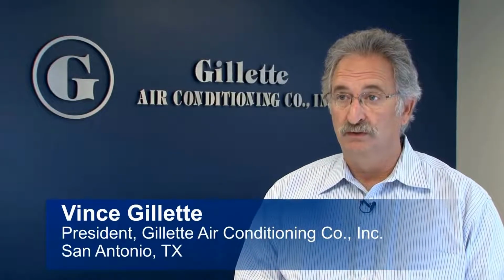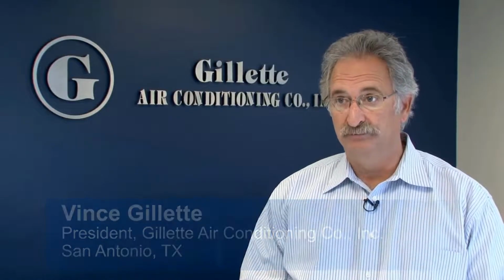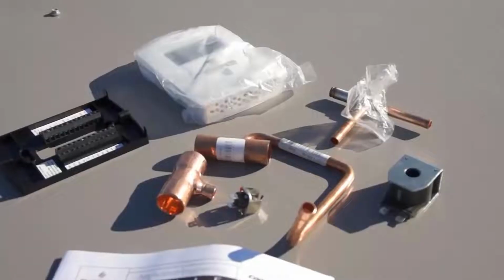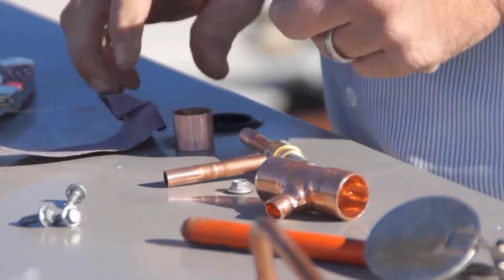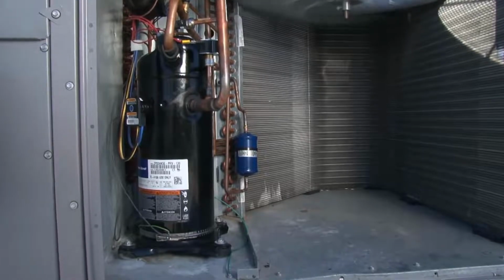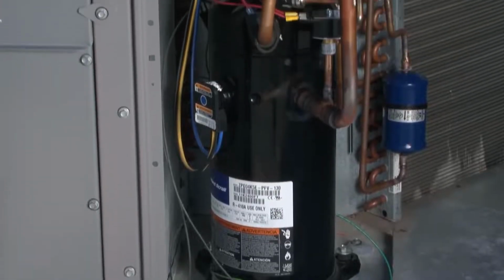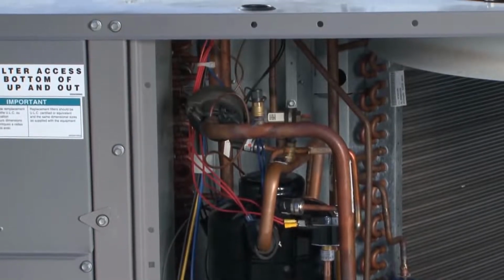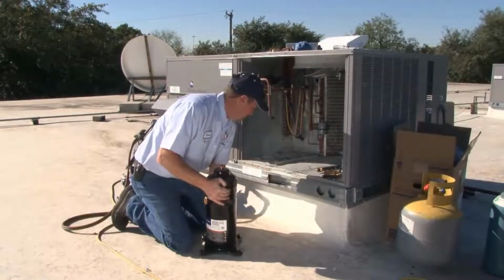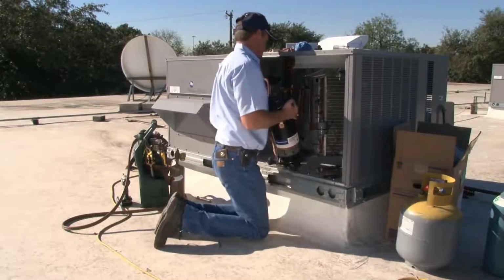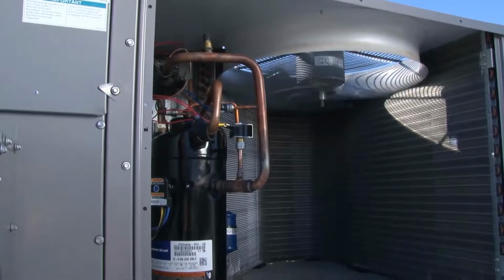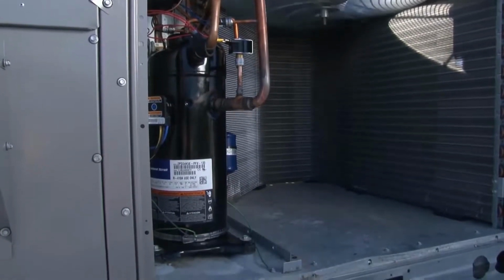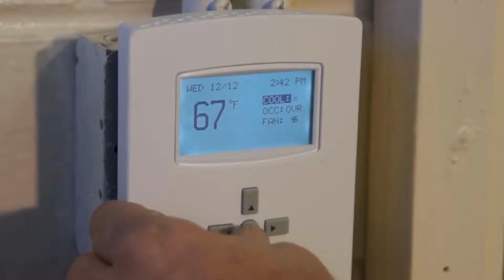We installed the digital scroll compressor with the new controller at a local school yesterday, and all the pieces that we received in the kit worked perfectly. We didn't have to fabricate anything. The unit started up, it ran just like it's supposed to. That compressor can be installed when you're in a replacement mode. When we have a dead compressor, using that kit, it doesn't take any more time to install that as it would to be installing a replacement compressor. The benefit for the customer is that he would have a modulating compressor. The unit would then match the load inside his building. And he would get a new thermostat that's programmable.